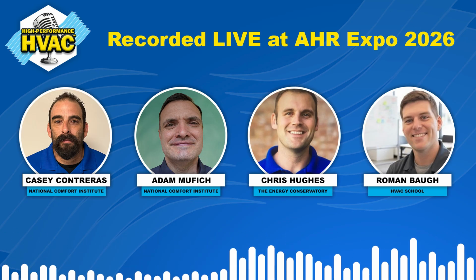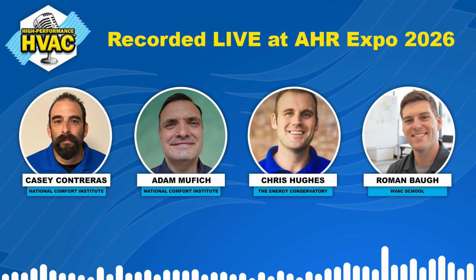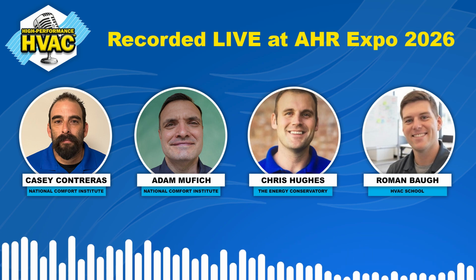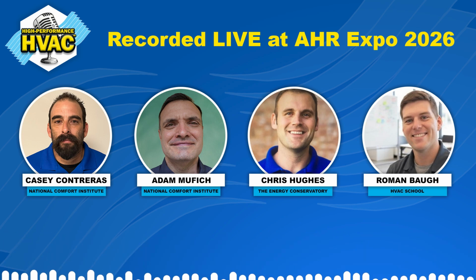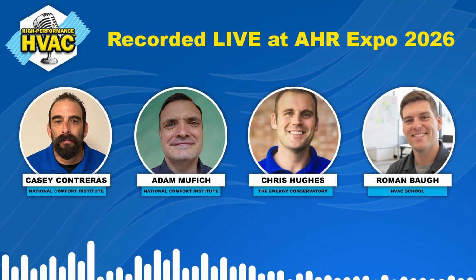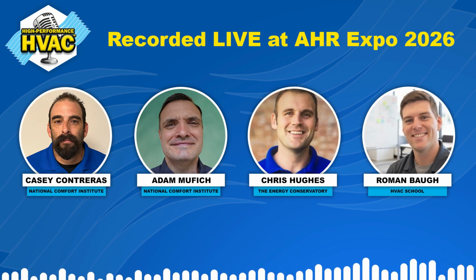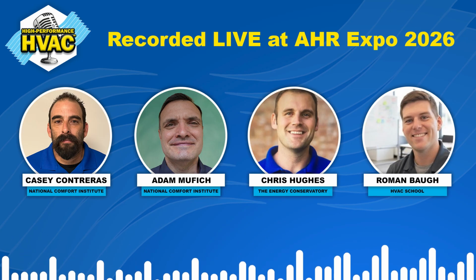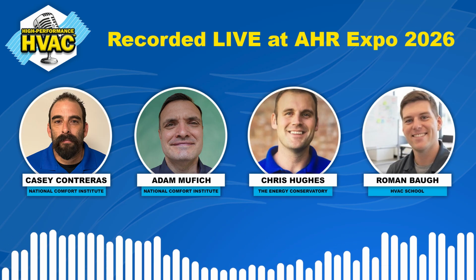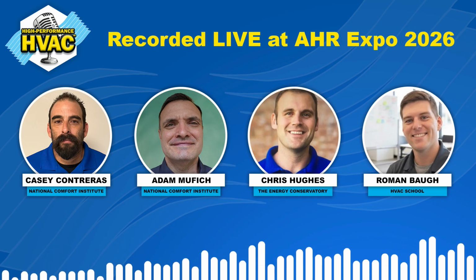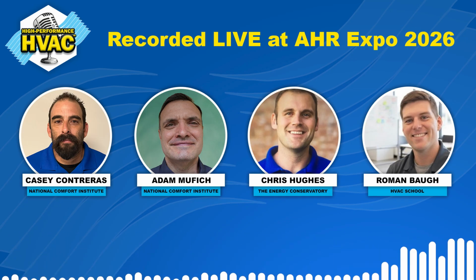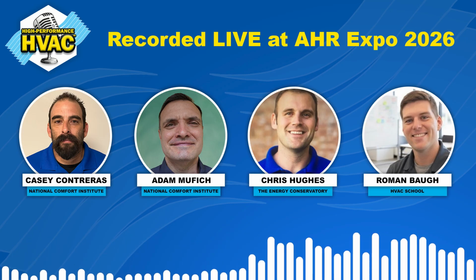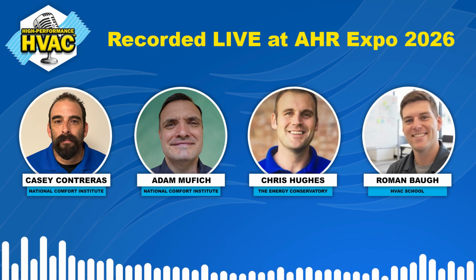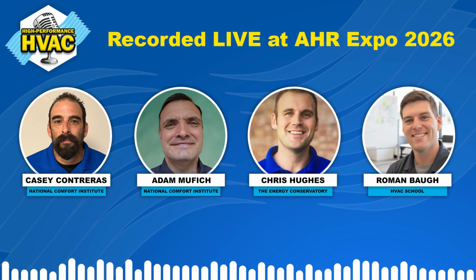Are you weighing it in and coming back in dead of summer to check charge? I have done both. So I'm very comfortable with just shooting from the hip and just doing exactly what I know it's supposed to do, and then looking for the things that I know make sense, and that is suction superheat, discharge superheat, and system subcooling. Again, a system is going to balance at some point on all the sides, right? The outdoor expansion valve is going to stop going up and down. It's going to stop in a sweet spot. So would you be running it in heat mode while you're doing this and trying to set this initial charge? So, yep.